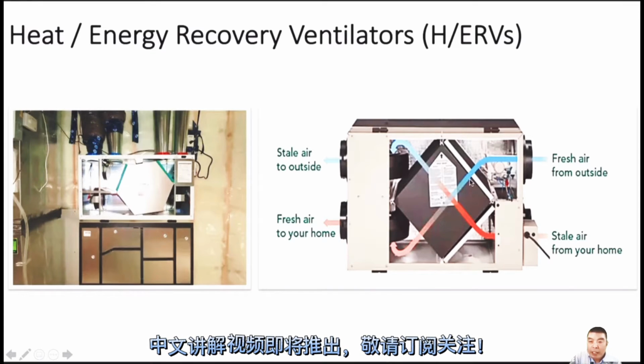We can see the colors. This is the cold, fresh air from outside, which goes through the heat exchanger and exchanges heat with the stale air from the house, because the house air is normally around 20 to 22 degrees, while the cold outside air may be minus 10, minus 20, minus 30. They exchange heat, so the air leaving the house is not that warm, and the air coming inside is not that cold. That is how they save energy and why it is called a heat recovery ventilator. The big thing is this heat exchanger, which makes the energy saving.